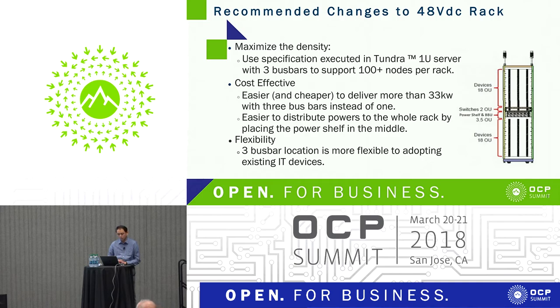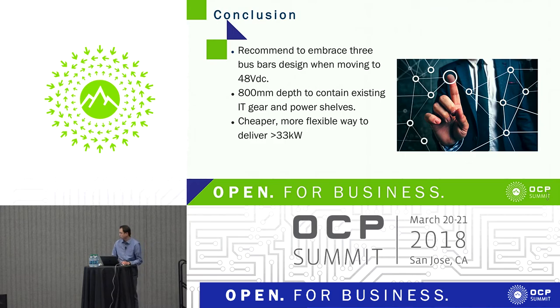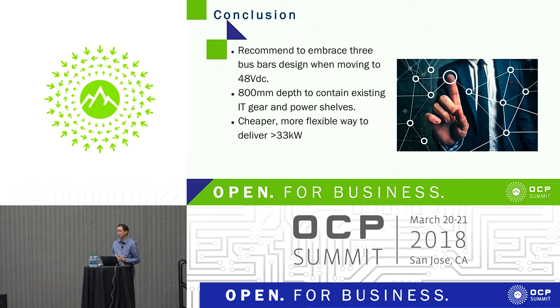Q: I'd like to see — not now, but later — a breakdown of the cost at the IT load all the way through, because you've increased the number of connections required and that connection cost is fairly expensive. A: Okay. In conclusion, we recommend still embracing the three bus bar design when moving to 48-volt DC, as we believe it is the most convenient, flexible, and higher-capacity design.